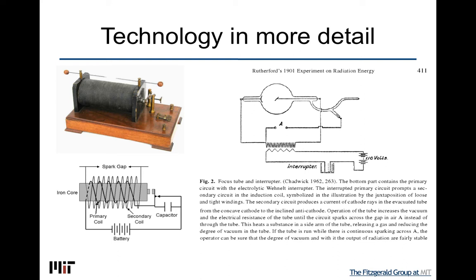And another thing is that as an operator, you can hear and see that the X-ray tube is working properly, because the spark gap has a spark going across it, and it makes a crackling noise. This was very important at the time. When you were making an X-ray photo, you might expose for 20 minutes, and then you would get the photo and you couldn't see anything, and only then did you know that the X-ray tube hadn't been operating properly. But here is a way of making it visible and audible that it's working properly, and that's really important.